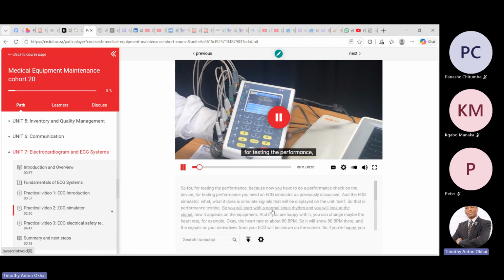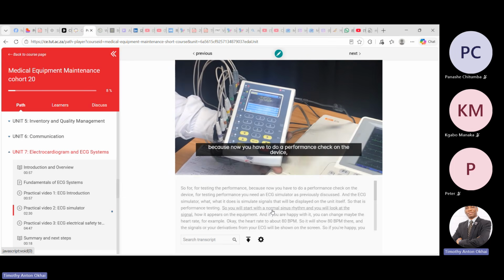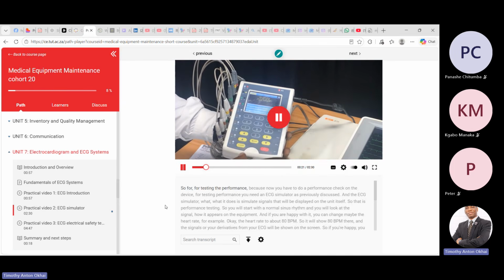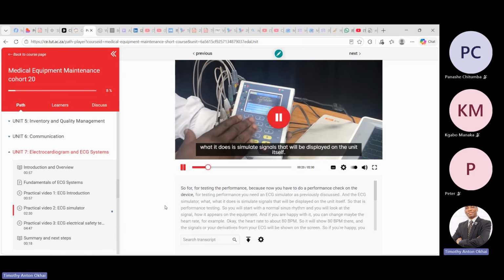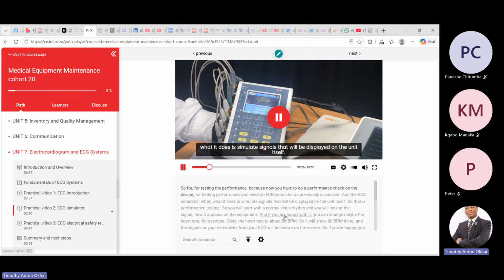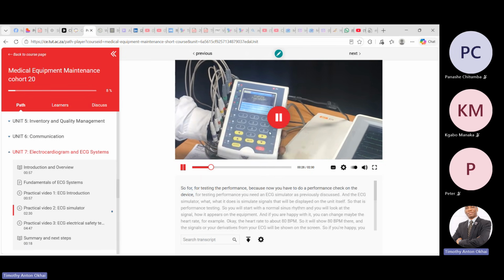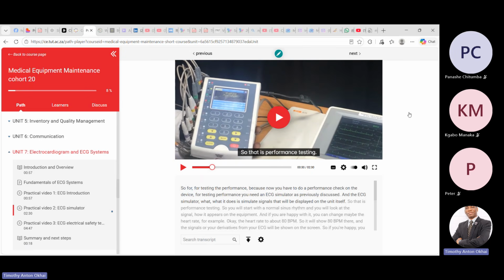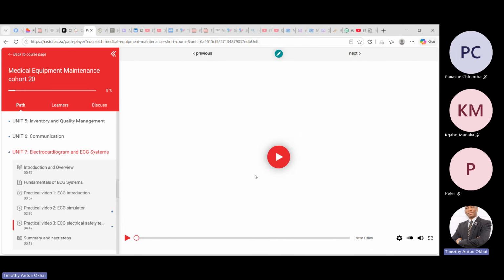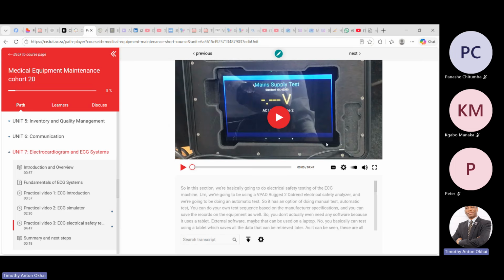For testing the performance, because now you have to do a performance check on the device, you need an ECG simulator as previously discussed. And the ECG simulator simulates signals that will be displayed on the unit itself. I will just pause. But the important thing here is to know where the navigation buttons are. You want to go back, you want to go to the next item, and you want to move away from here, go to another screen.